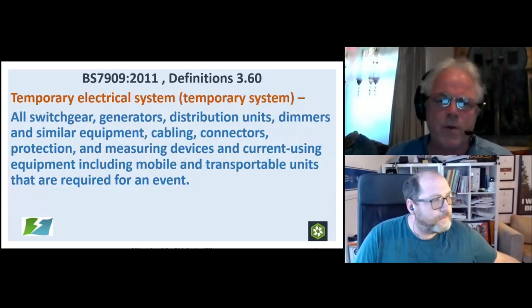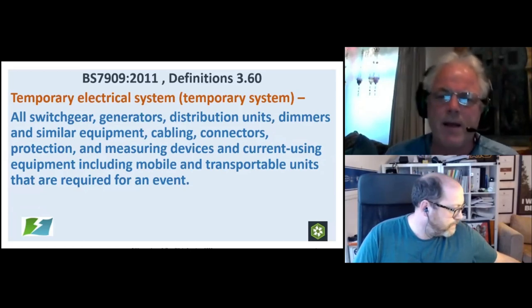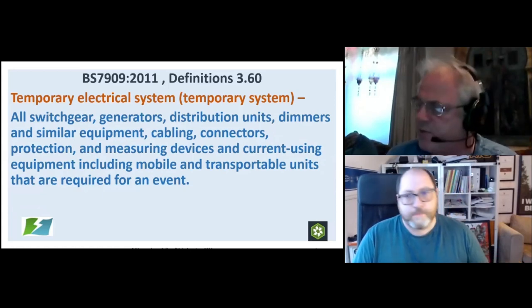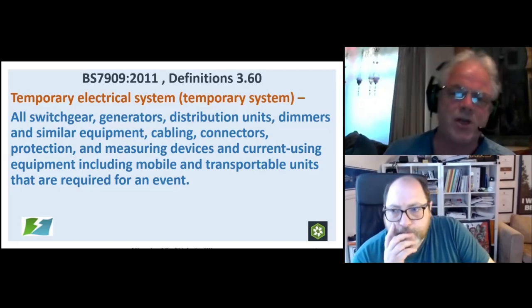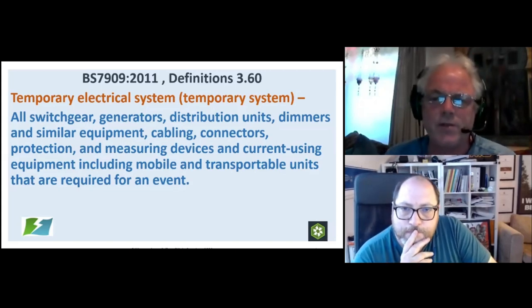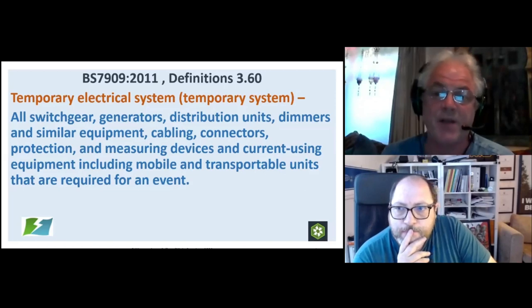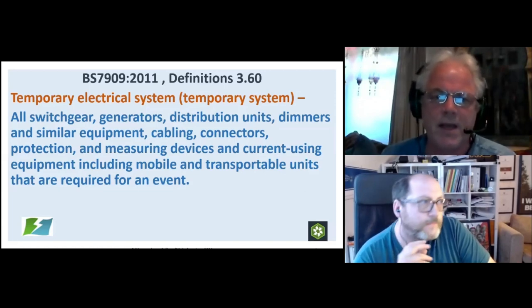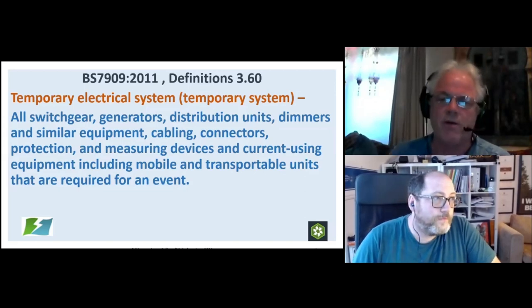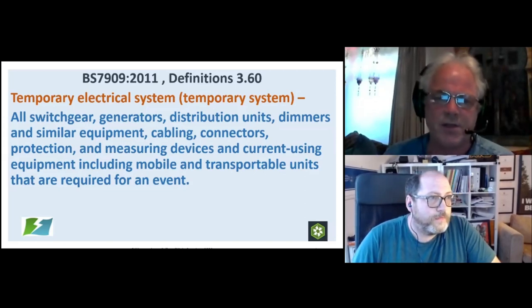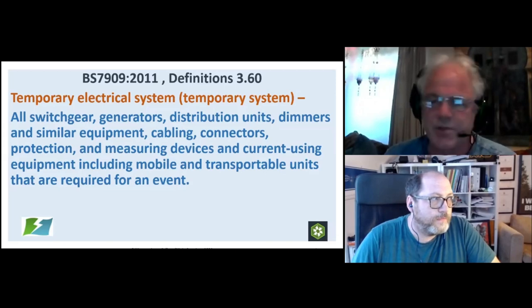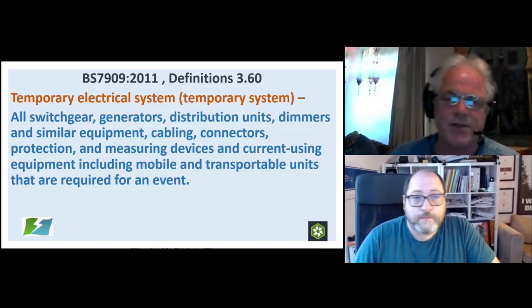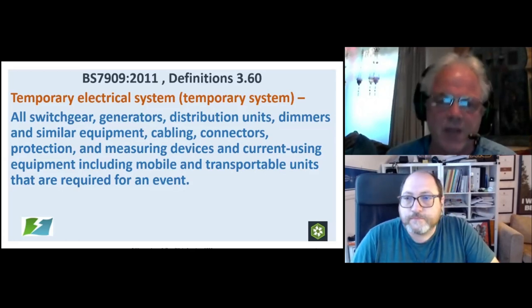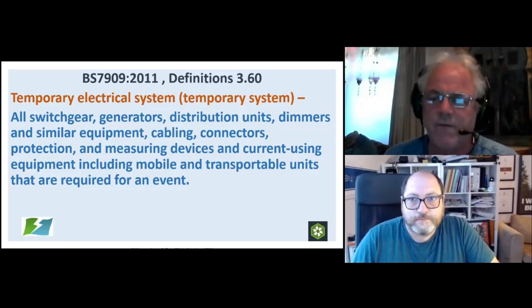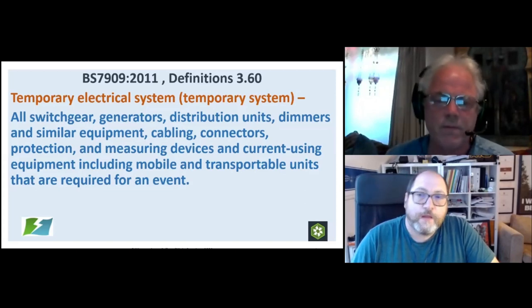We talk about temporary electrical systems, and they're careful with their wording. They talk about temporary electrical systems rather than a temporary electrical installation. 7671 talks about an electrical installation as being a fixed permanent install. That's why 7909 uses the terminology of temporary electrical system rather than installation. The temporary electrical system contains all your switchgear, generators, distribution units, cables, connectors, and everything else which is involved in providing a safe electrical system for the use of the event.